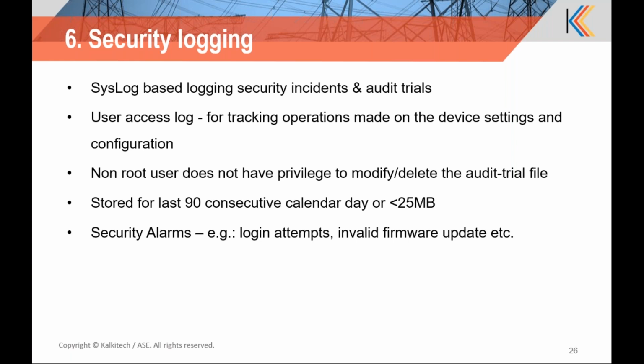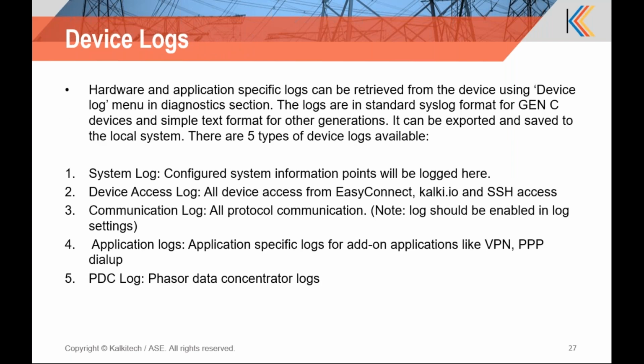any login, invalid login attempt, invalid firmware update, etc. triggers a security alarm, and that can be monitored from the center. Then device logs, there can be multiple types of logs. System logs can be there, device access log, protocol communication log based upon protocol communication channel. Then application specific log like VPN, PPP dial-up logs can be there. Phasor data, if you are using it as a phasor data concentrator, phasor data concentrator logs are also available in the system to monitor the stuff and control the access based upon whatever is the deviation of action that took place.